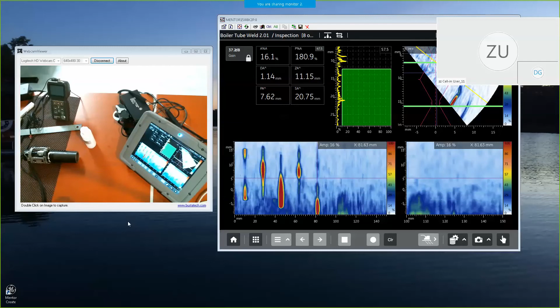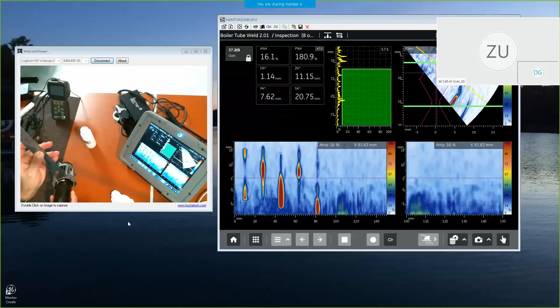So that's the boiler tube application, combining this clever scanner that snaps around the tube. Here I was holding the scanner and turning the tube, but in the field, in an actual boiler, you would snap the scanner on and then move the scanner around the pipe. It's a nice low profile device, so you could get this between adjacent tubes that were no more than, I would say, 3/4 of an inch apart.